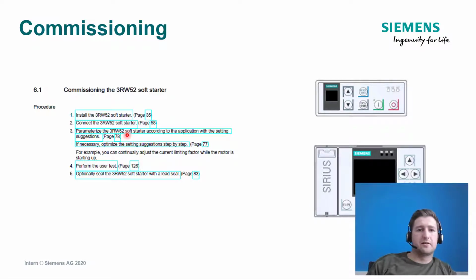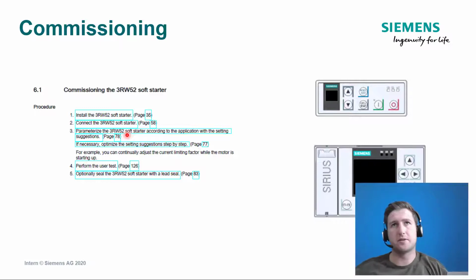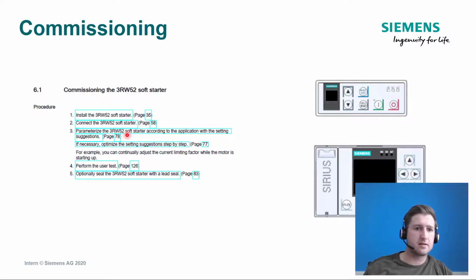And then the next voltage parameter would be the ramp down function. With the ramp down function, you would set the amount of time you want the motor to coast down to 0, and we could set that potentiometer anywhere from 0 to 20 seconds. And then the final potentiometer is the current limitation function. The current limit function won't allow you to go above a certain current rating during the startup.